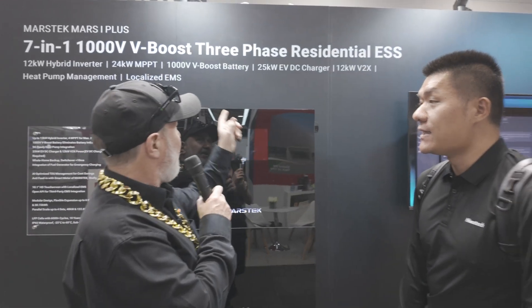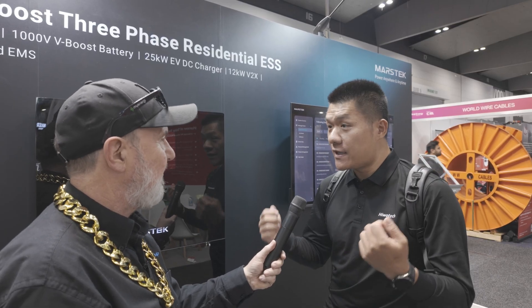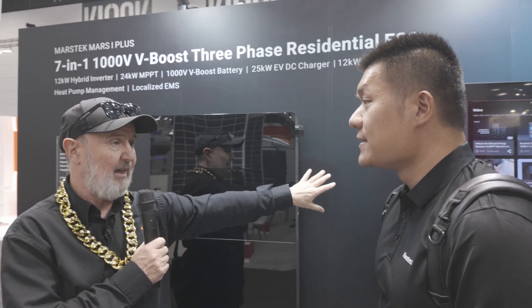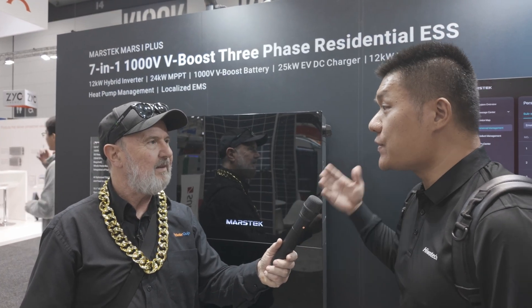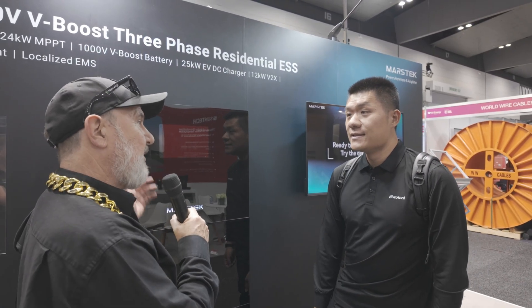It features a 1,000 volt V-boost battery. David explains this is unique: the most advanced EV cars now carry an 800-volt charging platform, so Marstek offers a 1,000 volt EV charger to work with those vehicles through an external connection. Moreover, the battery-to-battery and battery-to-hybrid-inverter voltage is 1,000 volts, which further reduces efficiency losses. Internally the batteries may be around 50 volts, but a DC-DC converter steps up to the 1,000 volt DC bus.